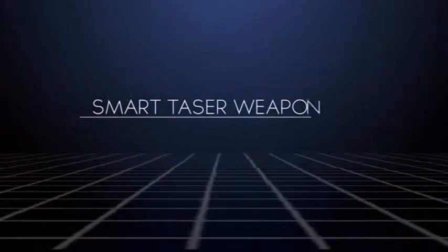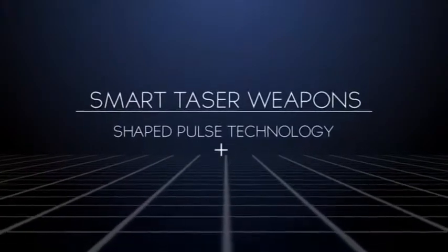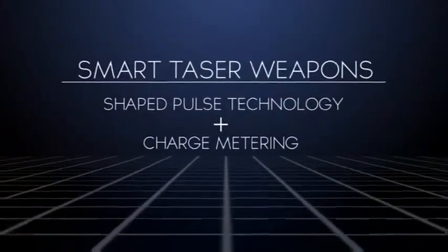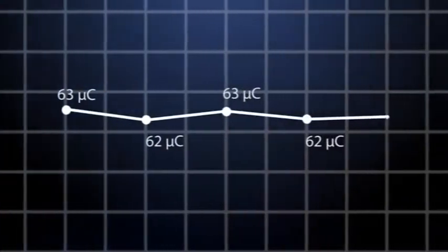These smart TASERs use enhanced shaped pulse technology with charge metering, an advanced calibration system that measures and adjusts the output of each pulse. Inside the 2003 model X26, an analog gas tube controlled each output pulse. There was no way to measure or adjust the magnitude of the electrical output, which was fixed at one factory setting.